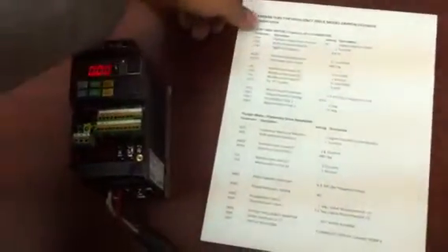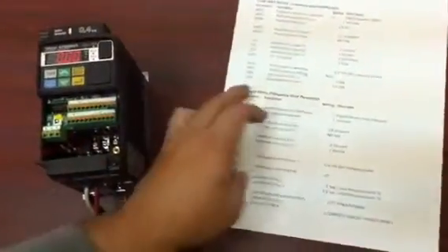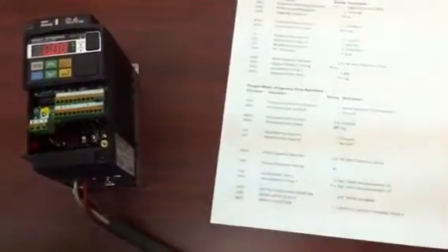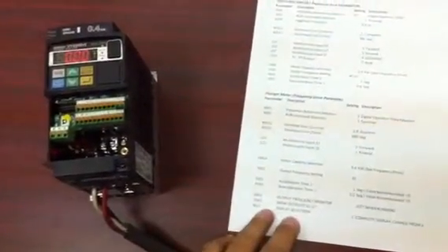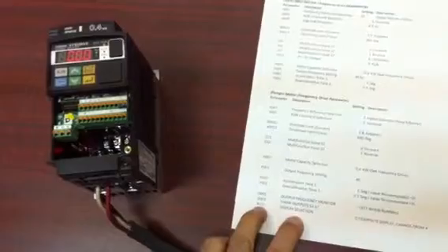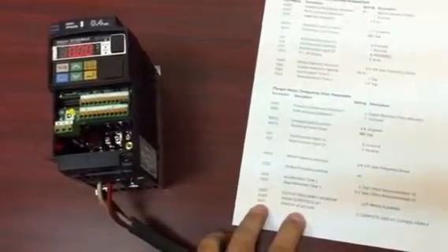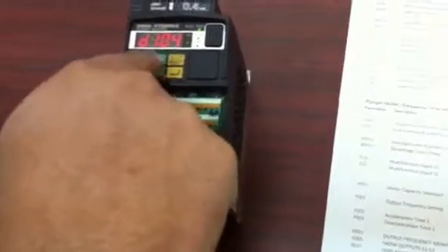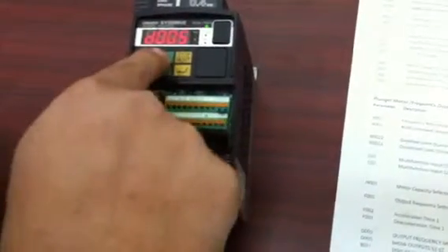On this list, the first part is the turntable motor parameters, and the second part is the plunger motor parameters. The first thing we need to do is change parameter B037, so it's going to show us the complete list of parameters. When the system is from the factory, it only shows certain parameters, not all of them. So by clicking the blue button, I'm going to browse to parameter B037 first.